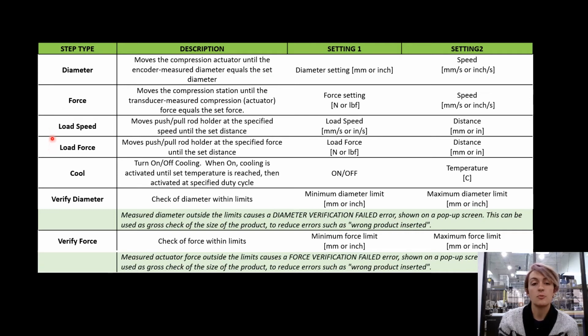The next two settings, the load speed and the load force steps, are both settings that control the auto pushrod loader. In the first case, the load speed step is a control for how quickly the auto pushrod loader is moving. The set point here, setting number 1, your load speed, tells the machine that you want it to travel that fast regardless of how hard it has to push on your stent to maintain that speed. Setting number 2 would be the distance that you want it to travel. Conversely, if you choose the load force step, you'll be controlling the force that the pushrod puts against your stent. In this case, setting 1 would be that force, and the machine will run at whatever speed is necessary to maintain that force. Setting 2 would again be the distance that you want it to travel.